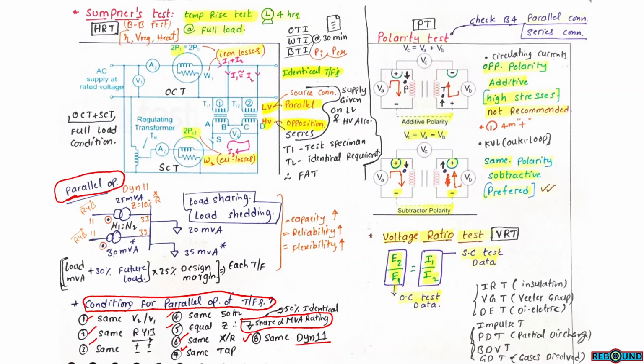Here we are considering our initial load is 20 MVA. For this load, we have installed a 25 MVA transformer. At a later date, the load is increased. 35 MVA additional load is added to this bus. So for this additional load, the 25 MVA transformer is not sufficient.